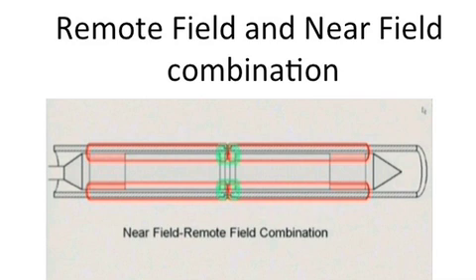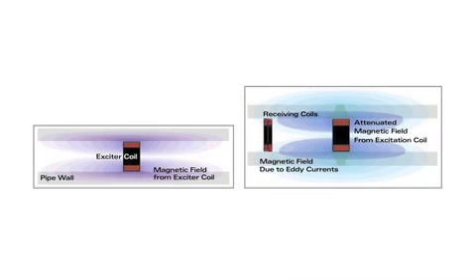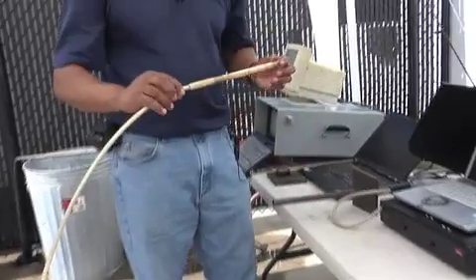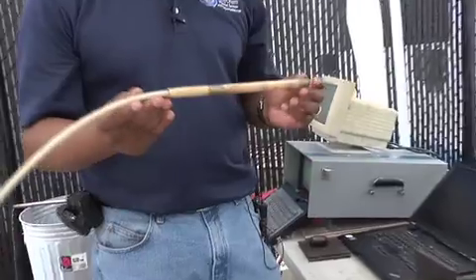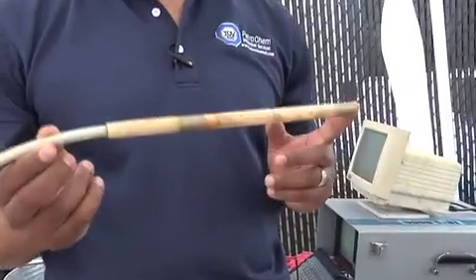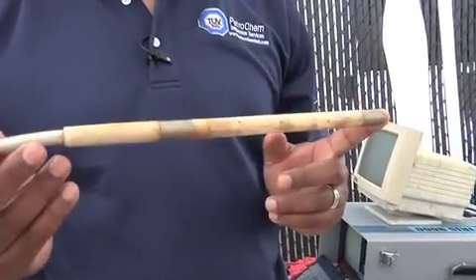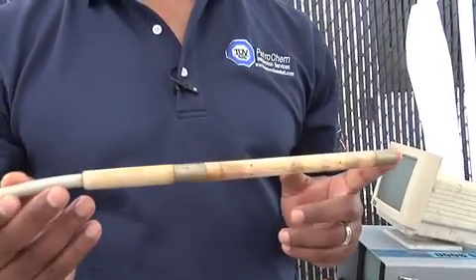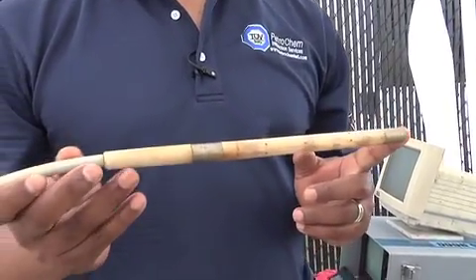The RFT is designed to inspect tubes that are highly ferromagnetic, like carbon steel, 2205, or 400 series stainless. This instrument uses a combination near-field RFT method.